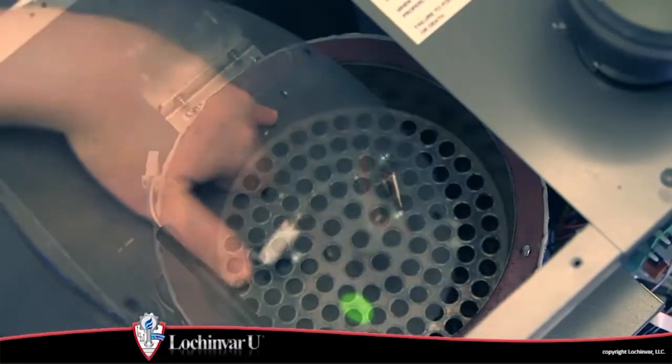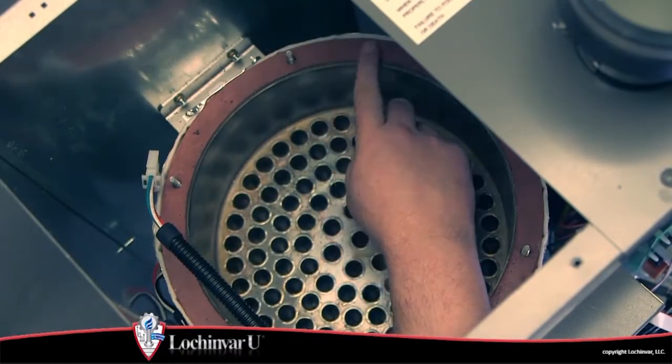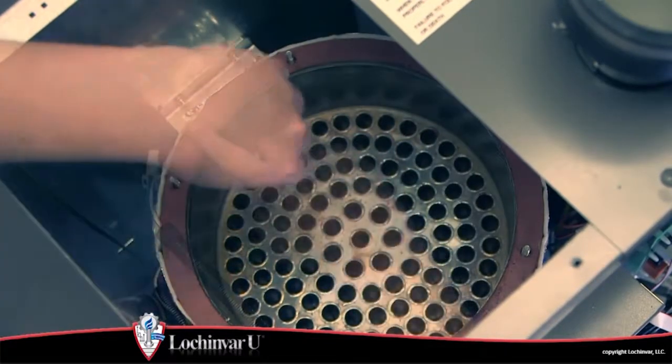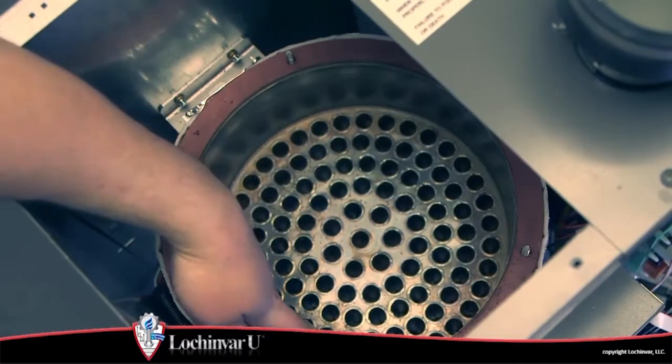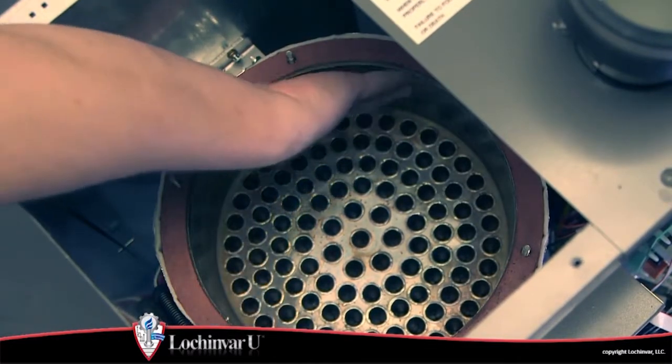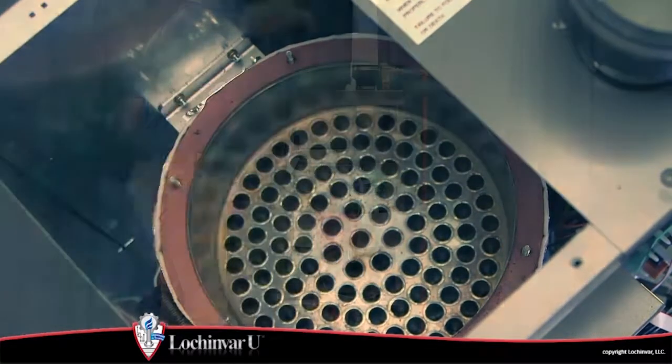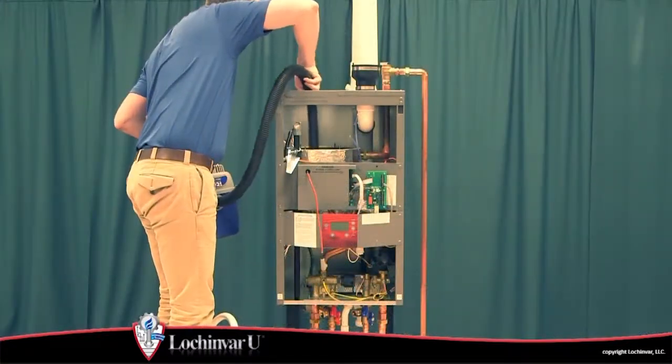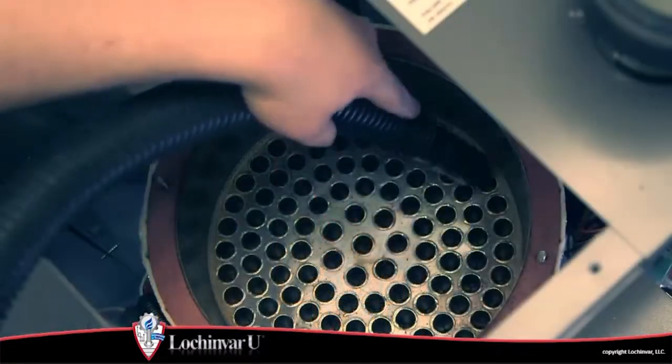A gasket is used to seal between the heat exchanger top plate and the heat exchanger. Now inspect the heat exchanger surface and combustion chamber wall for any soot deposits or dirt accumulation. Using a vacuum cleaner, remove any loose debris from the heat exchanger.